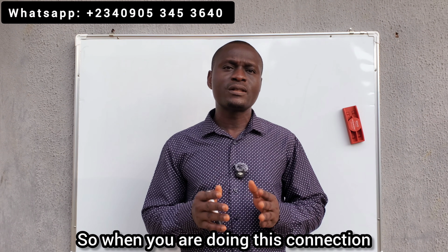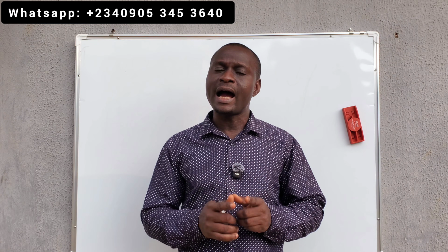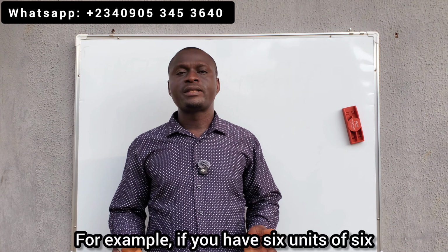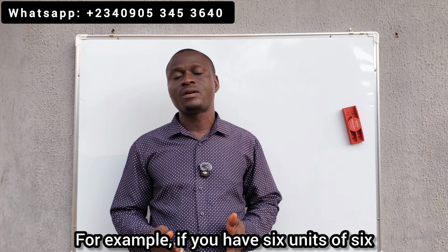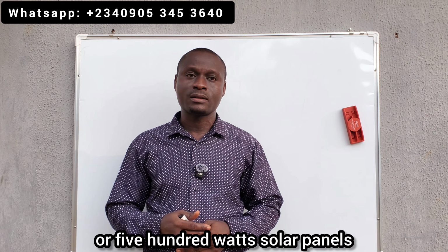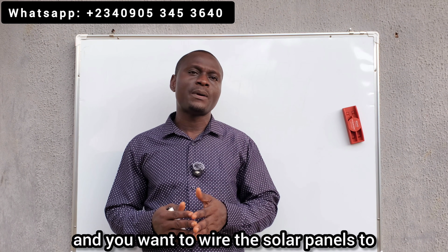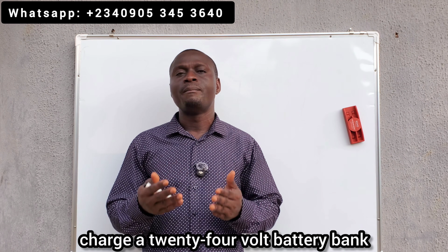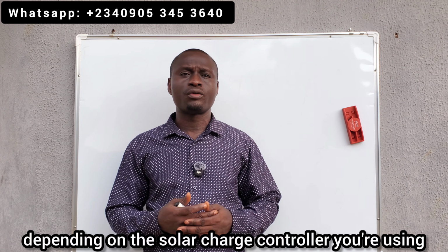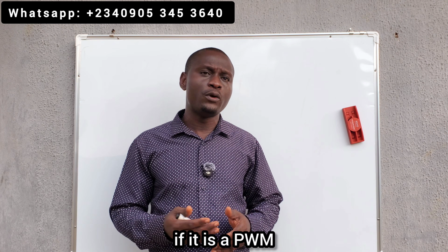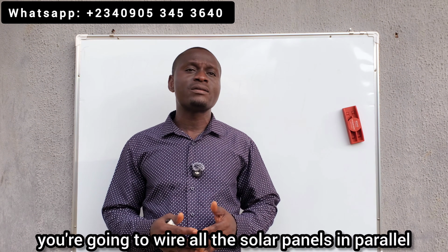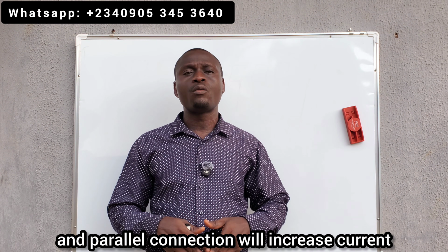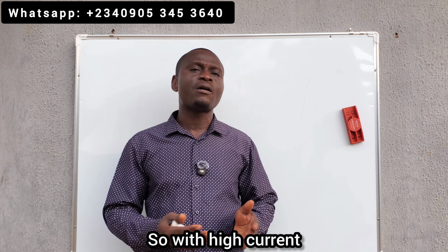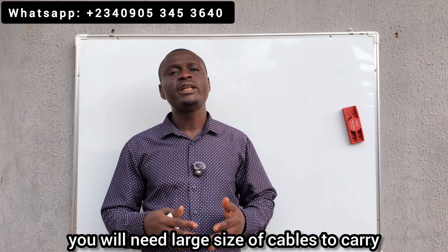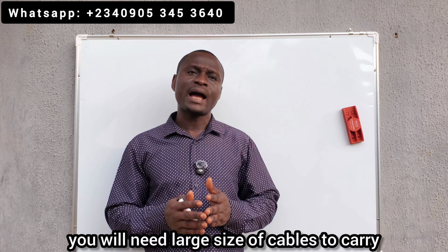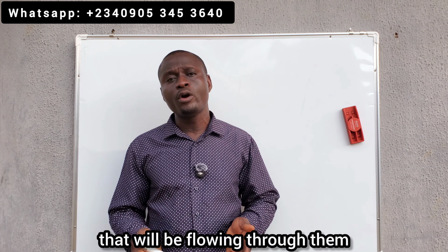So when doing this connection, you should be careful of the kind of cable you are using. For example, if you have 6 units of 600 watts or 500 watts solar panels, and you want to wire them to charge a 24-volt battery bank, depending on the solar charge controller you're using, if it is a PWM, you're going to wire all the solar panels in parallel, and parallel connection will increase current. So with high current coming from the solar panels, you will need a large size cable to carry that current.